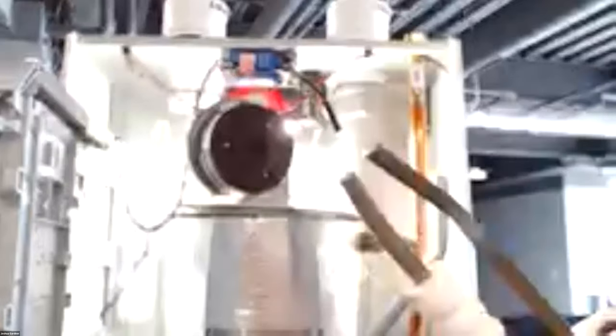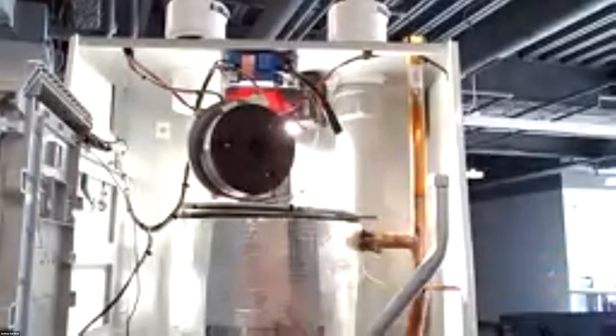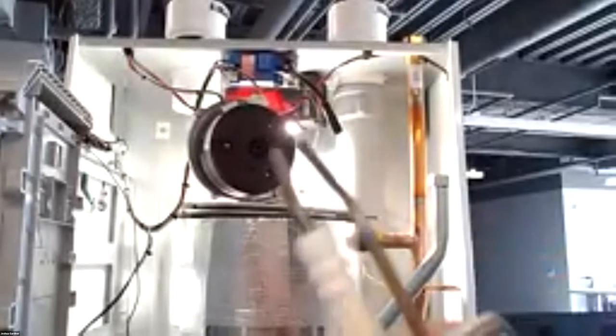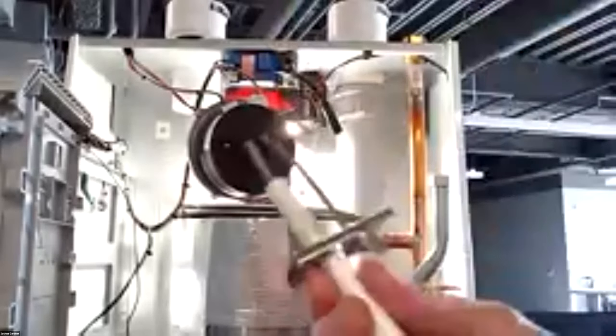We'll just take our igniter feed off, grounding wire. Pop my igniter out. Igniter gap, we're looking at about 1/8 of an inch separation. We're gonna inspect it, make sure it's nice and clean. A lot of corrosion, we'll just replace it. Also, when looking for sparking spots, if it's sparking up against here on the plate, if something doesn't look right, maybe it's sparking through here, I'll go ahead and replace that.